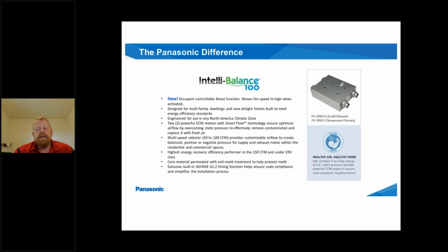Now the Panasonic difference: the Panasonic ERV has dual ECM motors for supply and return air. You can set those motors independent of each other in 10 CFM increments from 50 to 100 CFM. So you can dial in by square footage of the home and by amount of occupants in the home. The Panasonic does have a boost function. So if the occupants are having a party, they could walk over and flip a wall switch. That ERV will boost up to full supply, and it'll get more fresh air into the home to help offset all the stale air that's being generated because of the party.